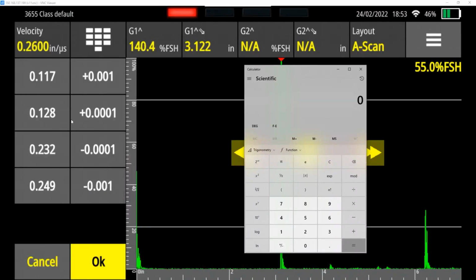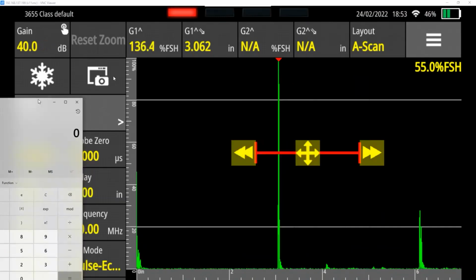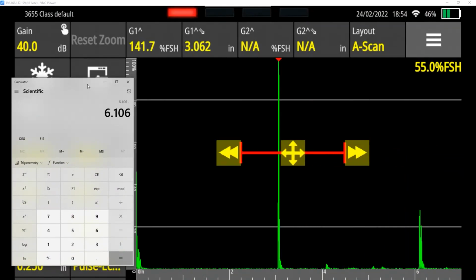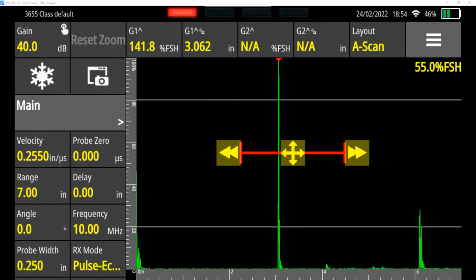So I'm going to adjust my velocity again. And I'll bring it down to 0.255. Okay. So if I set it at 0.255, I go over the small peak, I've got 6.106. And then I subtract the large peak, 3.062. And now you can see we're down to 44 thousandths, so we're getting closer, but we're still not quite there yet. So we need to adjust our velocity some more.